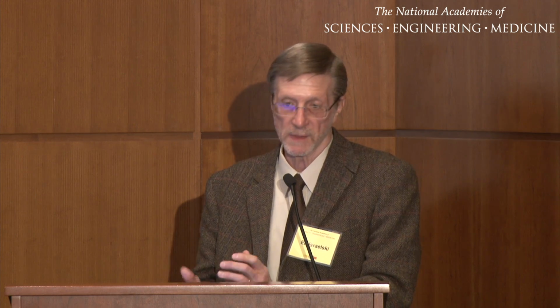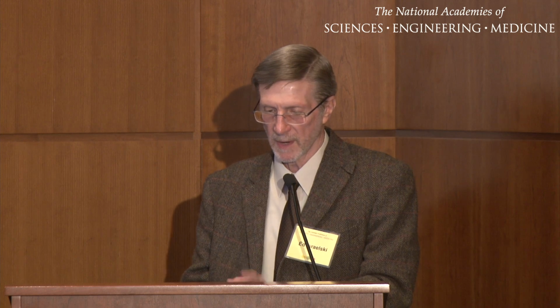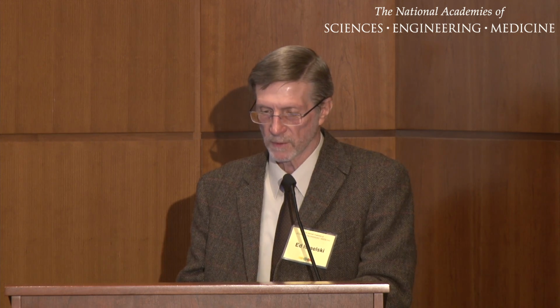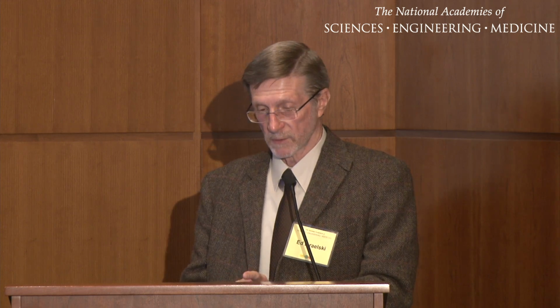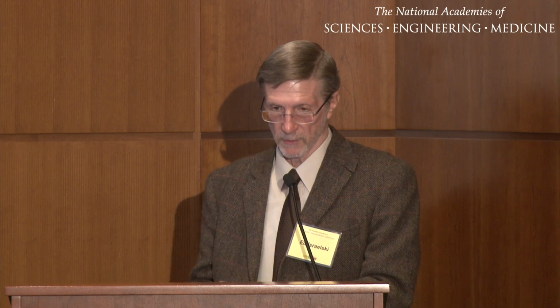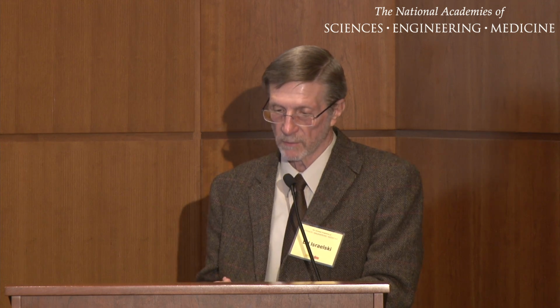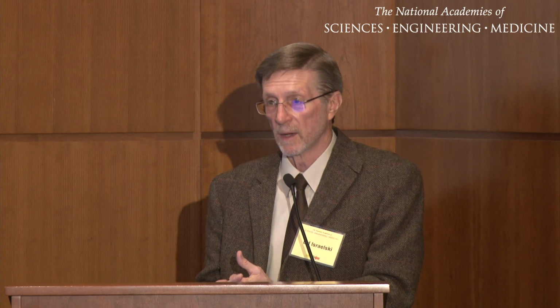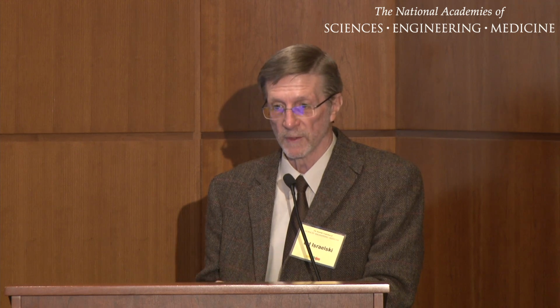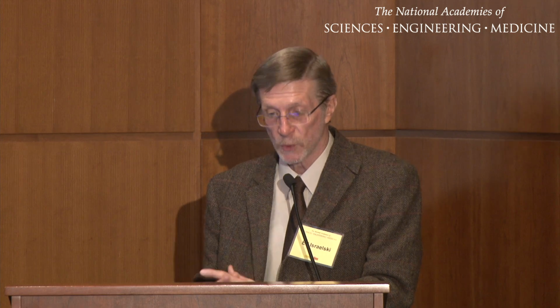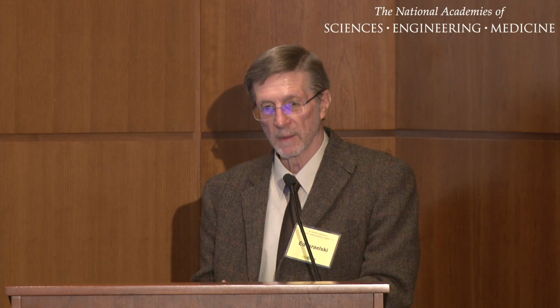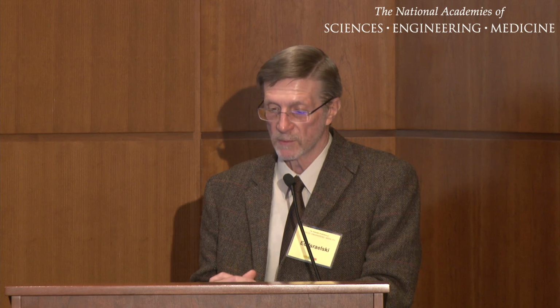And then there are two recently issued standards on the international level that are also domestic. Their full title is ANSI, AAMI, IEC 62366 Part 1 and Part 2. They're also ISO standards as well. The title doesn't reflect that, but they're joint standards between ISO and IEC. And I'm the co-convener of the group that has put these standards together, and we continue to evolve them. The first international standards actually came out on human factors, usability engineering, which is the preferred international term, in 2004. So none of this is new, but these are now getting more modernized, and they're reflecting more contemporary human factors language and usability engineering language.